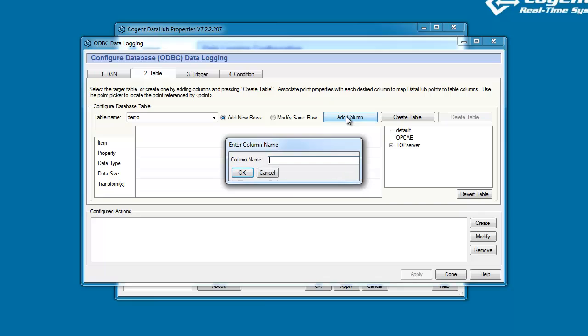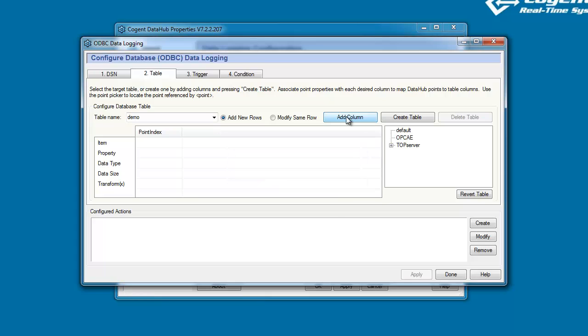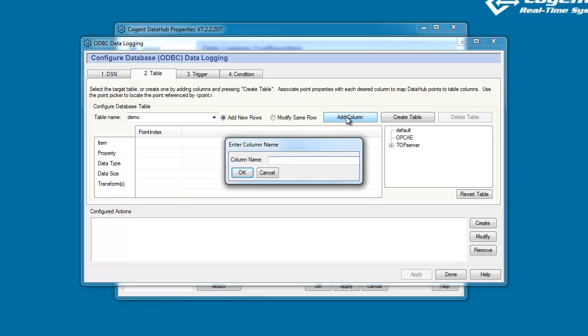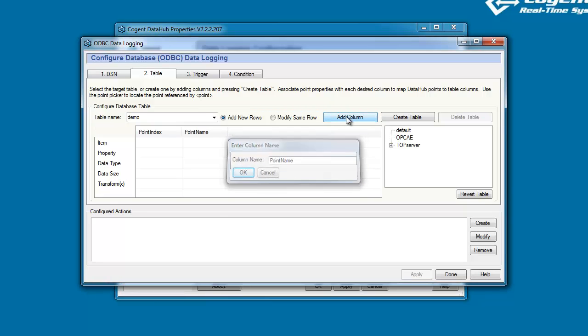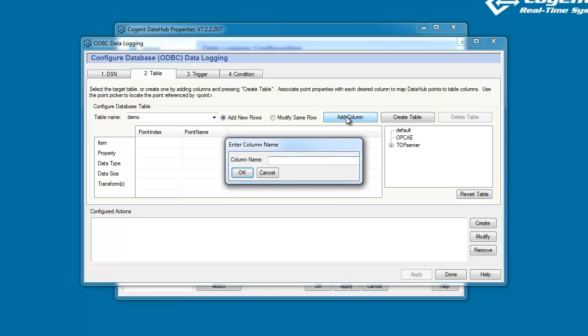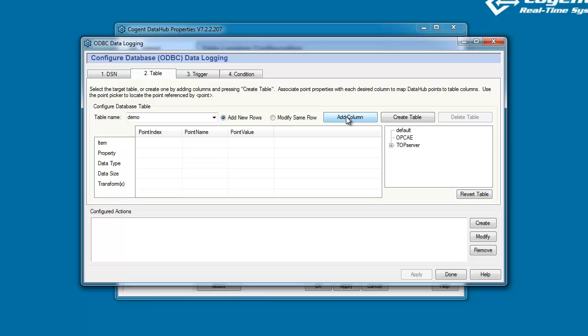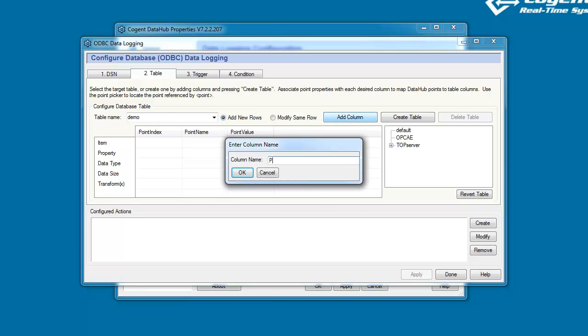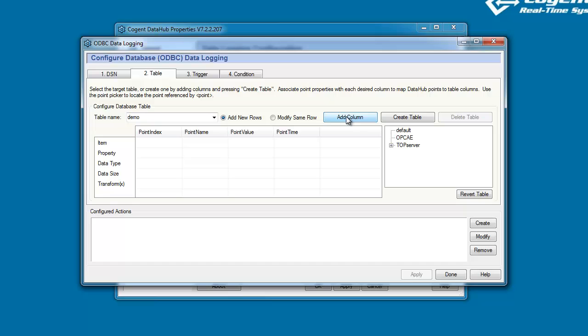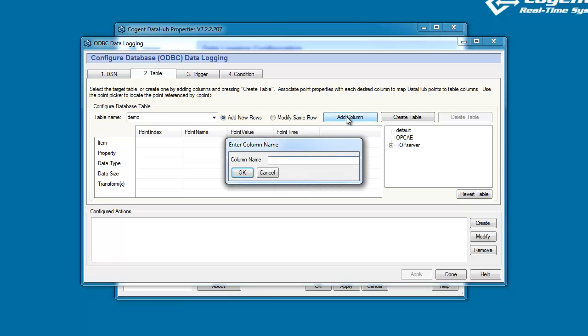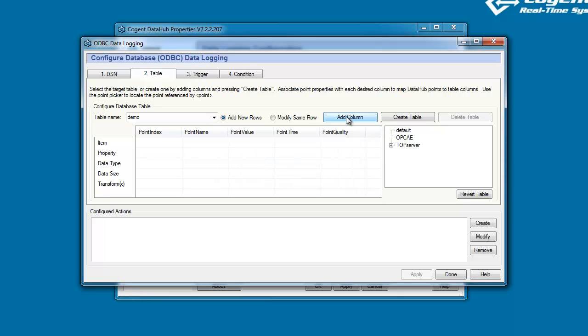I'll add the first column, and this I want to be an index column, so I'm going to give it a name of PointIndex, then I want a column for PointName, and another for PointValue, one for PointTime, and finally one for the PointQuality. So, let's define the names of the columns within our table, but before we go ahead and create the table, we need to define the data types for each of the fields within the table.